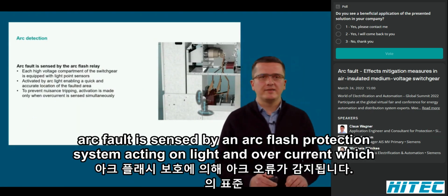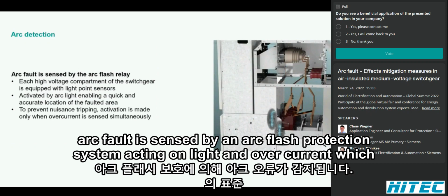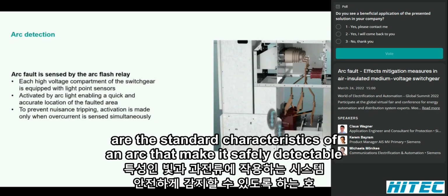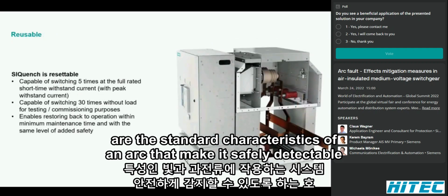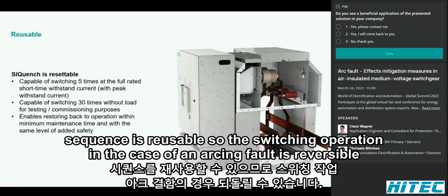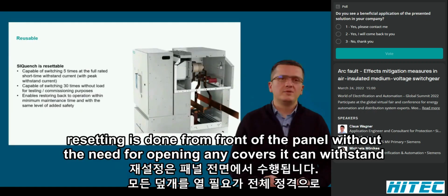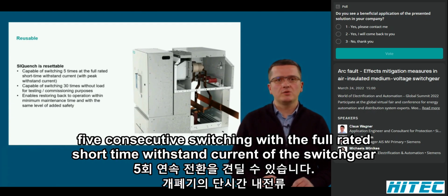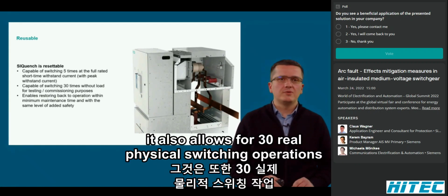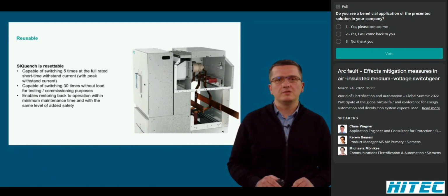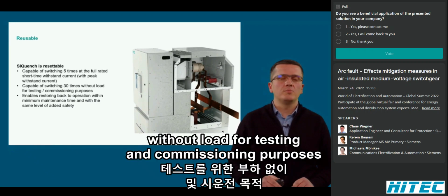Arc fault is sensed by an arc flash protection system acting on light and overcurrent, which are the standard characteristics of an arc that make it safely detectable. SiQuench is reusable, so the switching operation in the case of an arcing fault is reversible. Resetting is done from front of the panel without the need for opening any covers. It can withstand 5 consecutive switching with the full rated short time withstand current of the switchgear. It also allows for 30 real physical switching operations without load for testing and commissioning purposes.